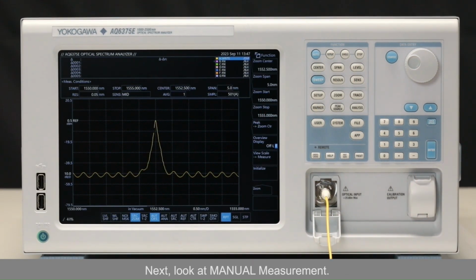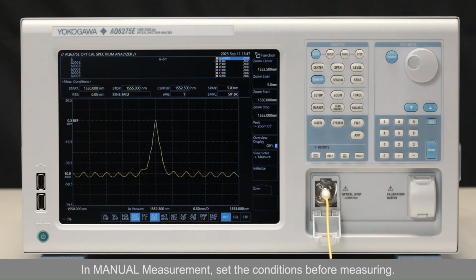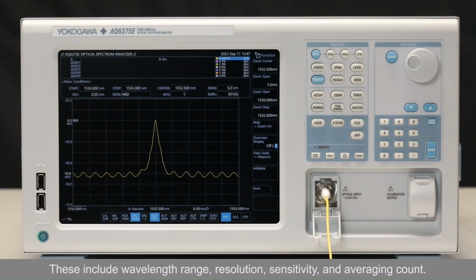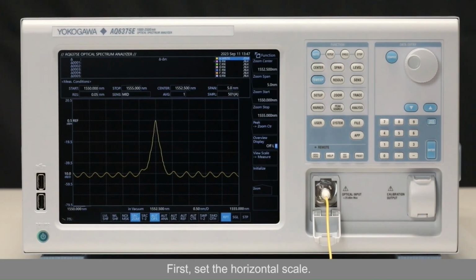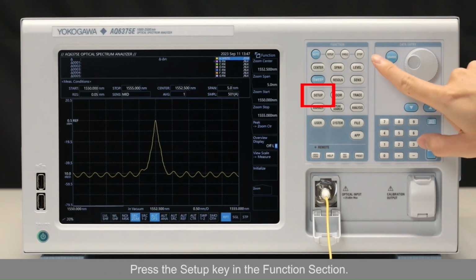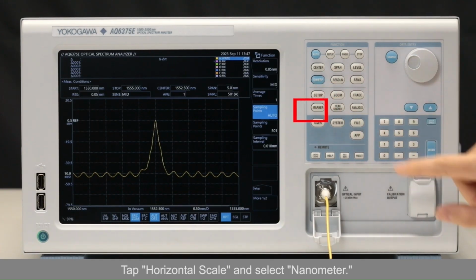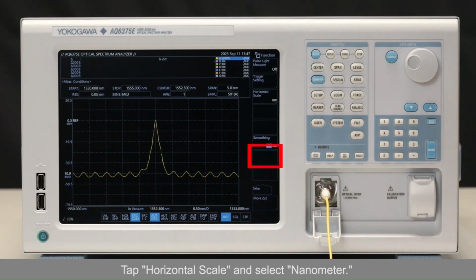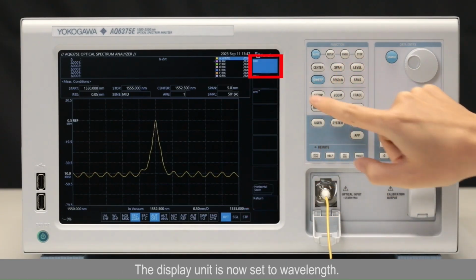Next, look at manual measurement. In manual measurement, set the conditions before measuring. These include wavelength range, resolution, sensitivity, and averaging count. First, set the horizontal scale. In this example, set the horizontal scale to wavelength. Press the Setup button in the Function section. Tap Horizontal Scale and select Nanometer. The display unit is now set to wavelength.